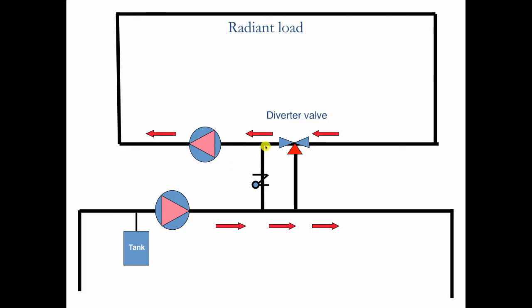It would cavitate with a three-way mixing valve, but it will not cavitate with a three-way diverter valve. So this is a pretty good way to do radiant heat.